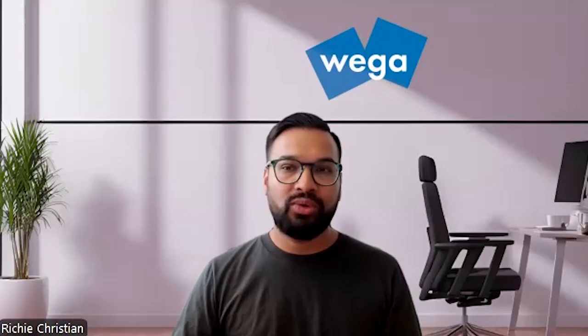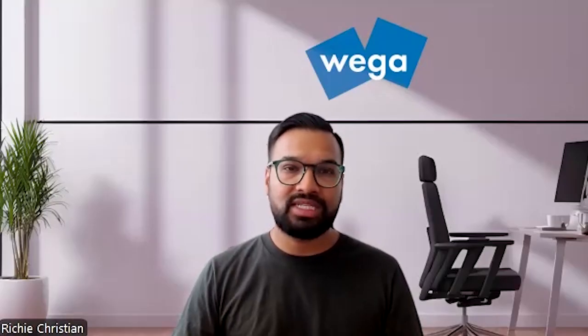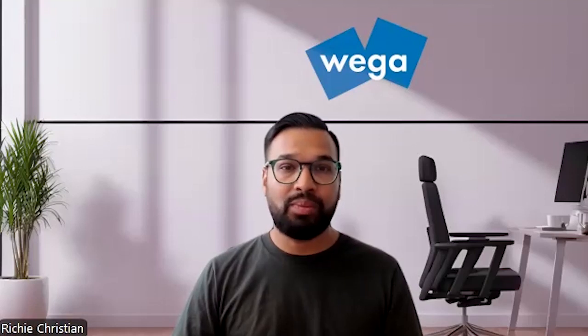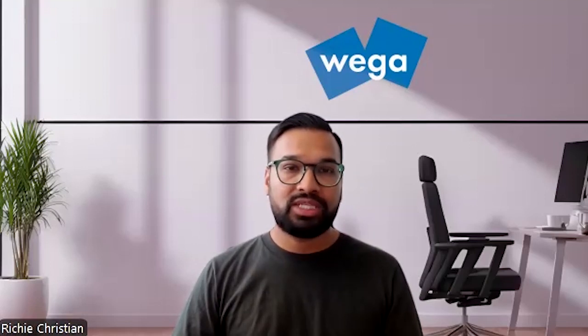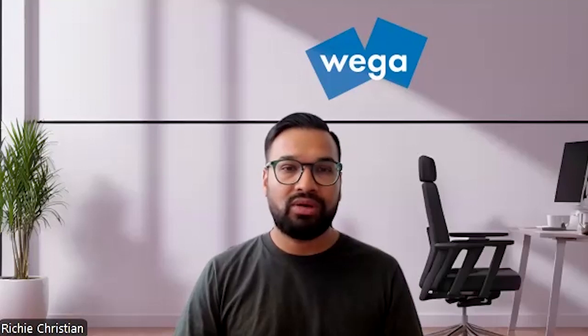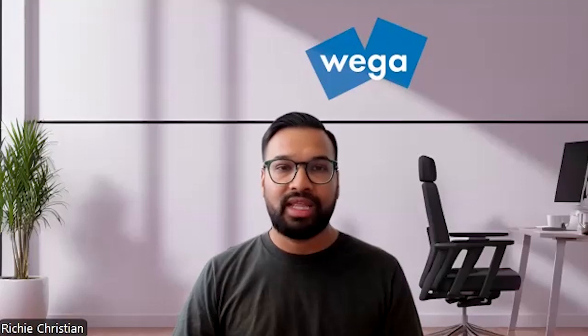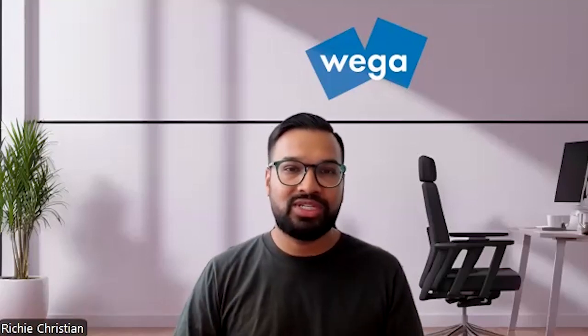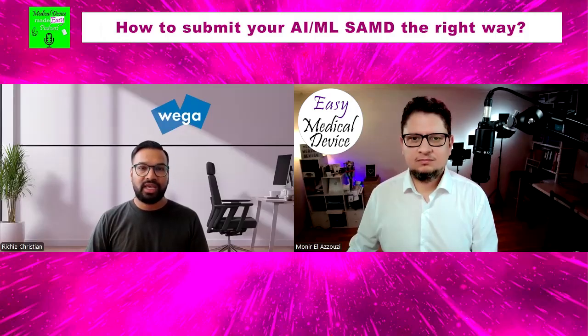So having made sure you think about this in advance matters, because it's really hard to address some of these last minute. They require a lot of time, a lot of resources, and many times external people to coordinate. So it's making sure that it's built into your regulatory strategy and your V&V plan, and going in, you're fully aware of what kinds of things are going to be expected from you. The submission is the last part that you just write, but it's really the thinking, the strategy, the collaboration, all of that going in together. That's what really gives you the success.